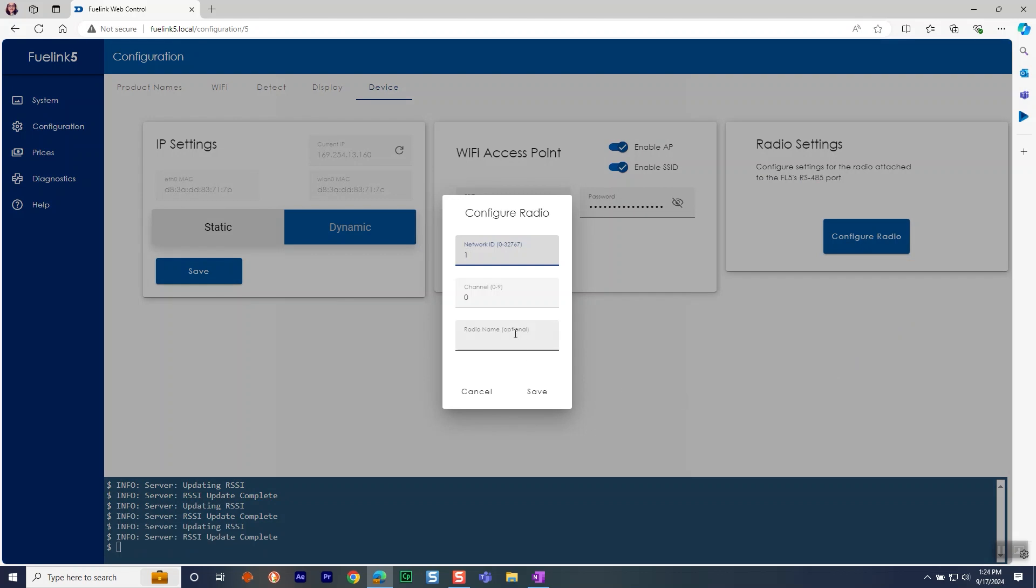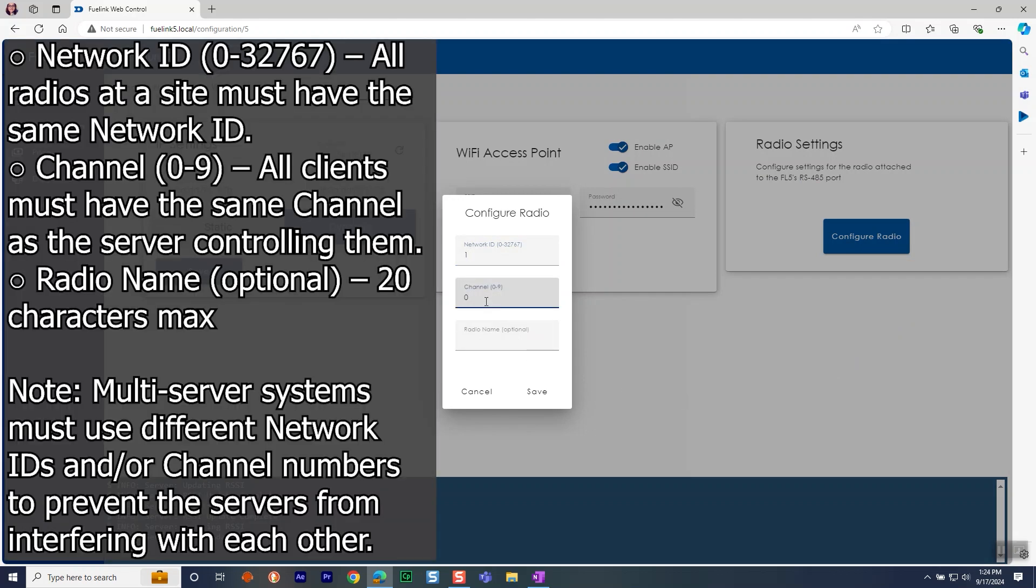Assign the following settings to each radio. The network ID, select any number in this range. All radios at site must have the same network ID. The channel is next. All clients must have the same channel as the server controlling them. You can go 0 to 9.